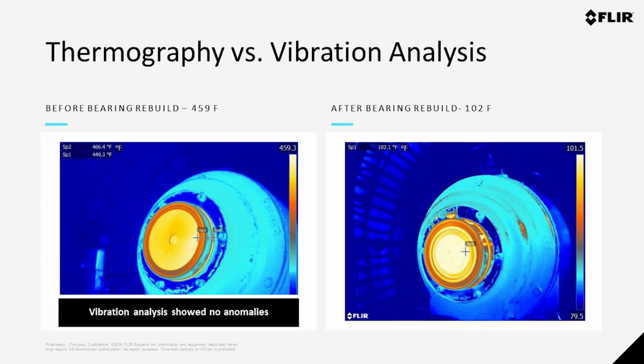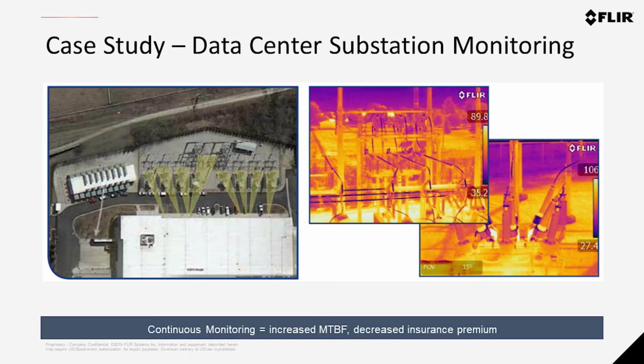So again, another example of where thermography is going to be able to give you meaningful information. And if that bearing is down from a motor, maybe that motor was showing that it was running hot also, and that could lead to further troubleshooting to see, well, let's see what else we find here. Maybe a bearing or something else is running hot. And indeed, that's what they identified.